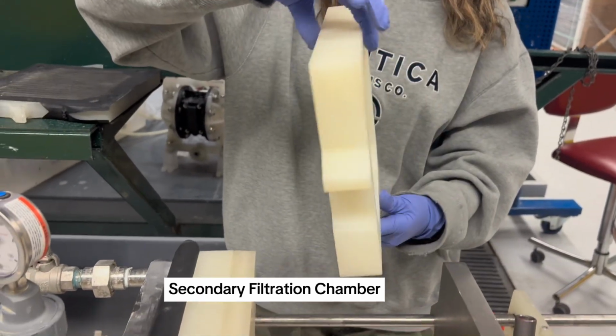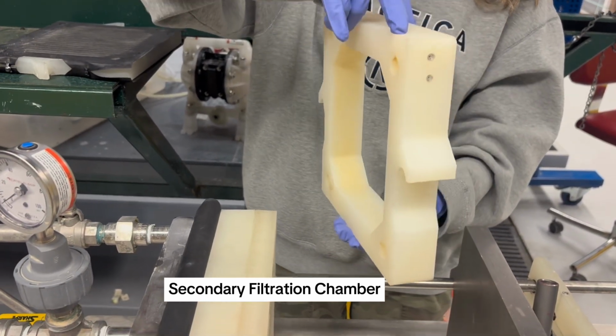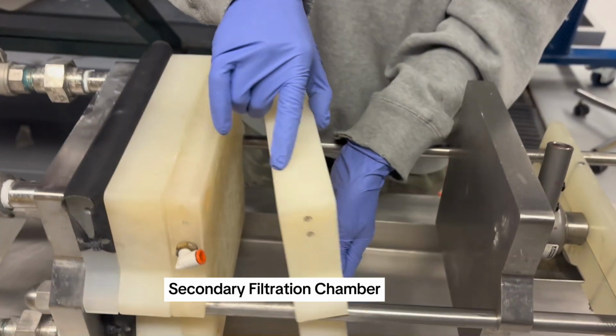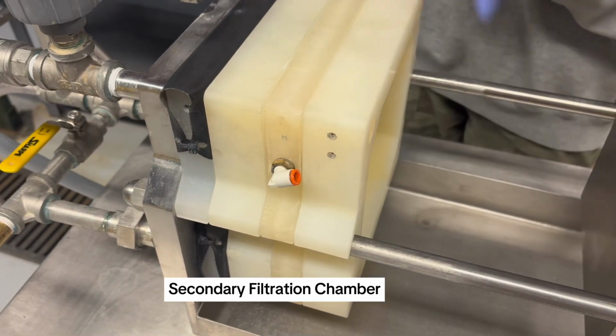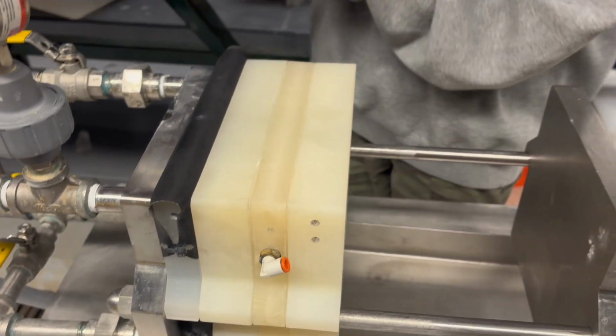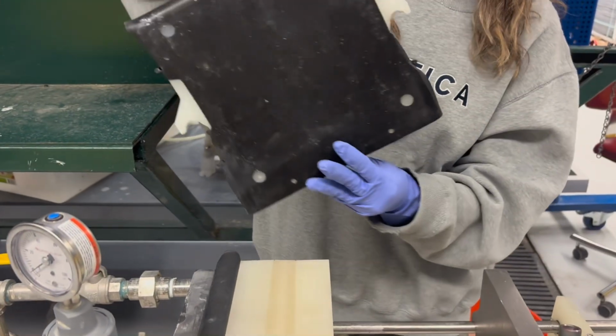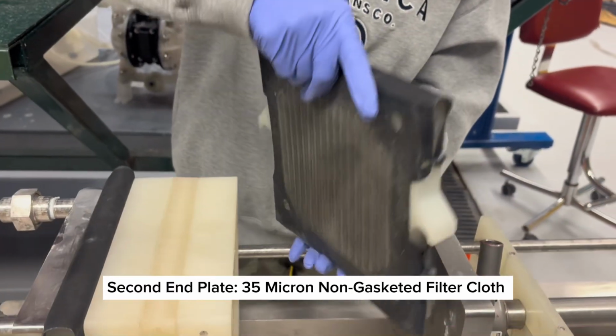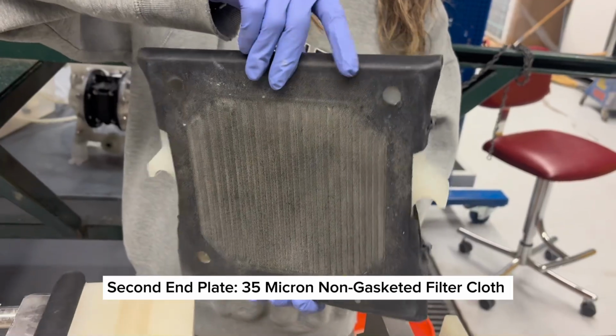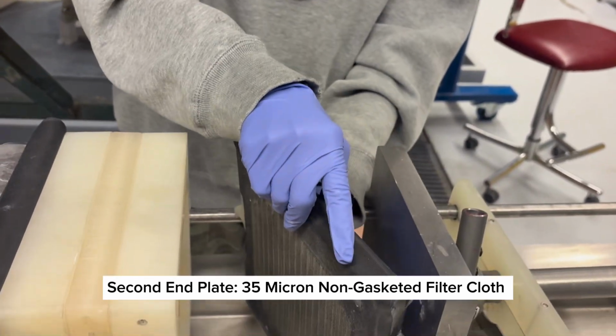The slurry then passes through a secondary filtration chamber. Finally, the slurry reaches the second end plate, also fitted with the 35 micron non-gasketed filter cloth.